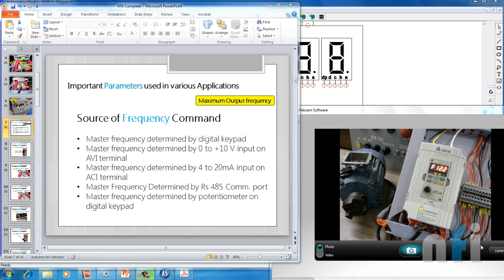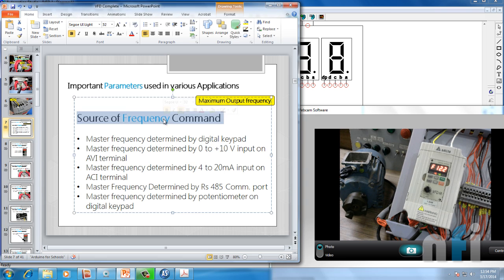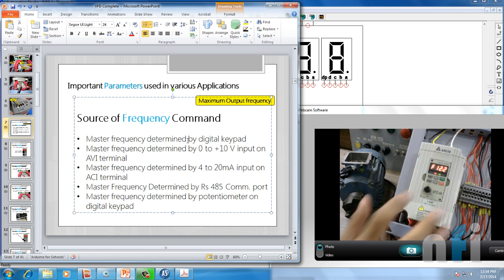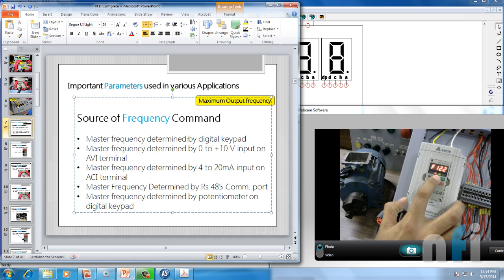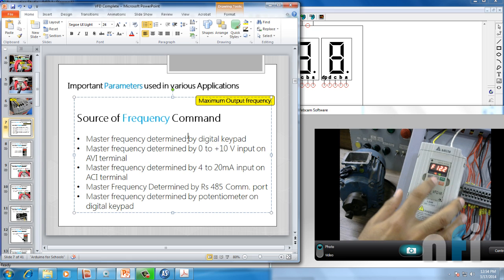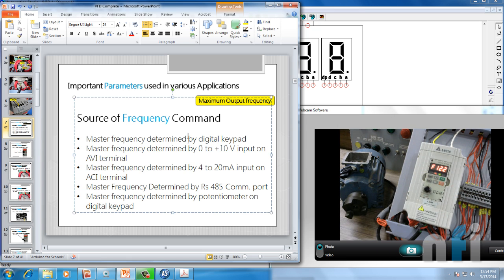Let's move on to the first parameter: source of frequency command. This controls how you want to control the frequency of your drive. We have various options. The first option says master frequency determined by digital keypad — this means frequency can be determined by this keypad. This is the increment switch, this is a decrement — we can control the frequency by pressing the switches.